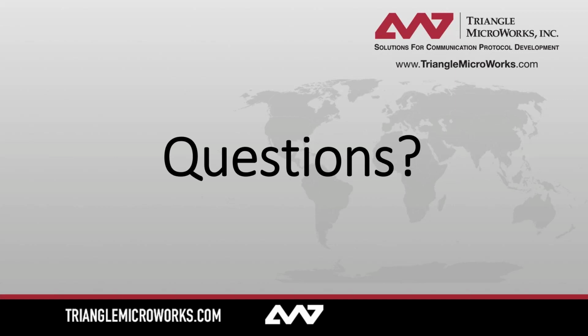Okay, next question. How does a gateway deal with a system disturbance event like a trip? So generally when a lot of events are all happening at the same time, there's a lot of buffering that goes on. You don't want to overload the bandwidth and have packets get lost or things along those lines. So it'll generally buffer up all of these events and send them out when necessary and when things cool down a little bit. So if a lot of events are all happening at the same time, you want to look into something like 61850, which supports buffered report control blocks.